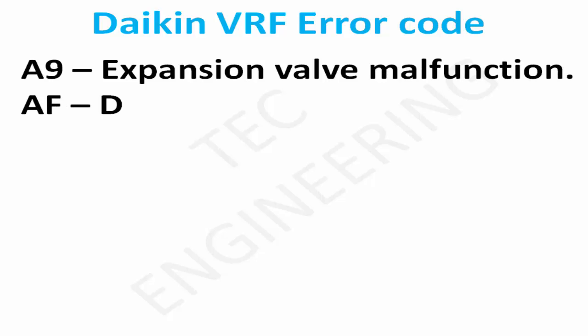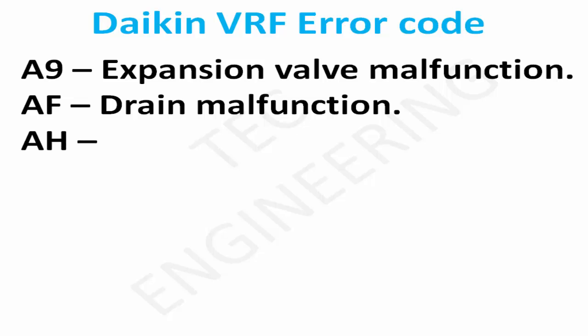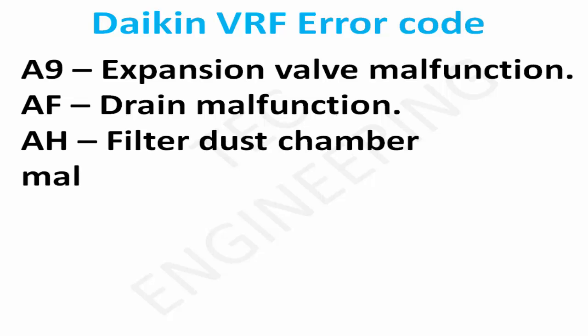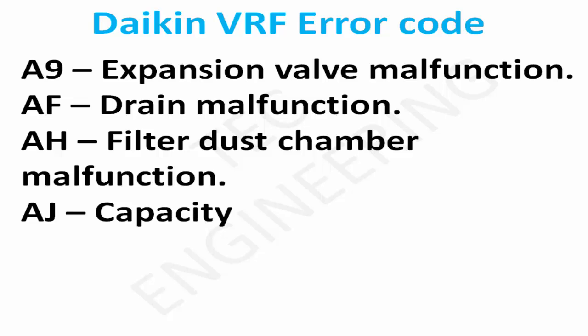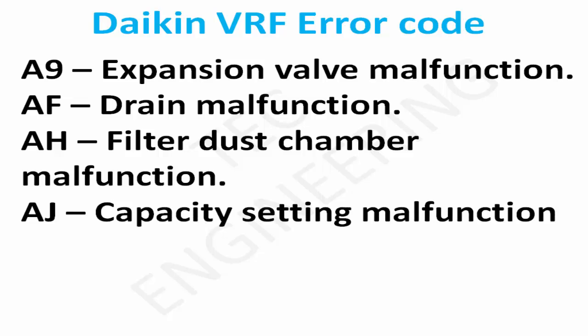AF: Drain malfunction, indoor unit. AH: Filter dust chamber malfunction, indoor. AJ: Capacity setting malfunction, indoor.